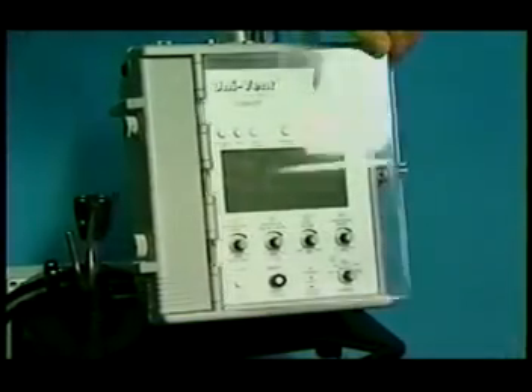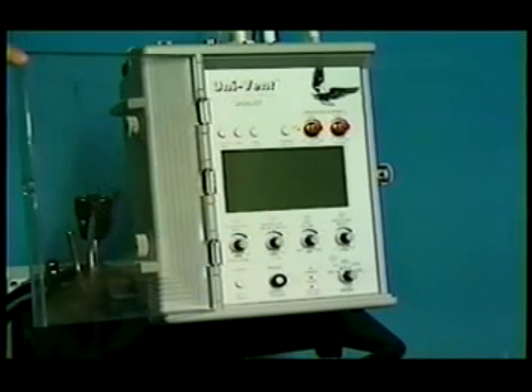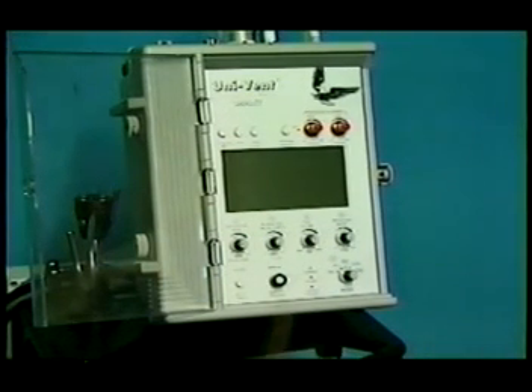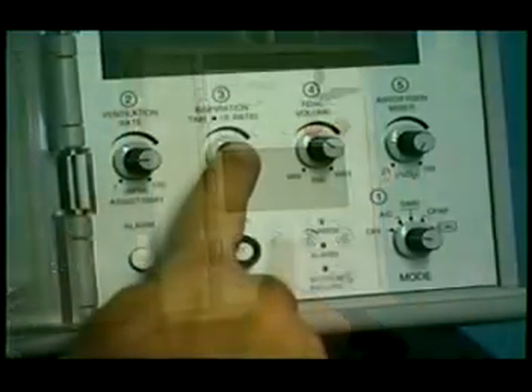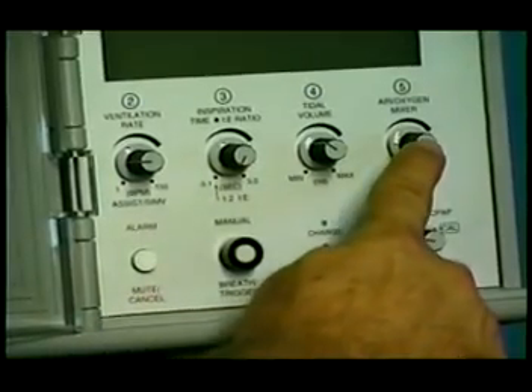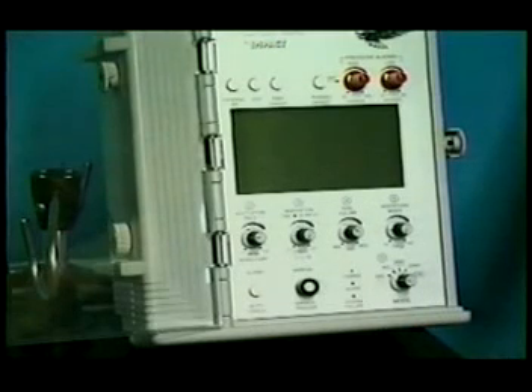To begin operation, unlock the clear hinged door by turning the locking knob counterclockwise, allowing the door to open. Look at the current position of each adjustable control. Determine whether or not any of the presettings need changing. For example, inspiration time, I:E ratio, and air-oxygen mixer. Do you want to customize certain settings? If so, you must access the User Program menu before operation.